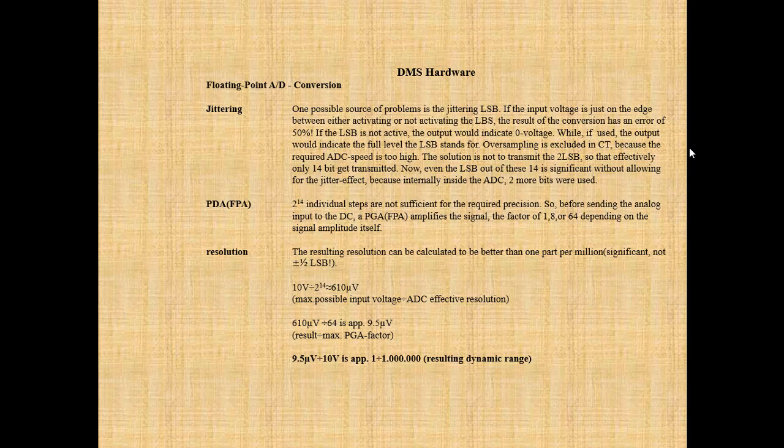Since 2^14 individual steps are not sufficient for the required precision, before sending the analog input to the ADC, a PGA/FPA amplifies the signal by a factor of 1, 8, or 64 depending on the signal amplitude. The resulting resolution can be calculated to be better than 1 part per million — significant, not plus or minus one half LSB. Calculation: 10V divided by 2^14 ≈ 610μV (ADC effective resolution); 610μV divided by 64 ≈ 9.5μV (maximum input resolution); 9.5μV divided by 10V ≈ 1/1,000,000 — the resulting dynamic range.